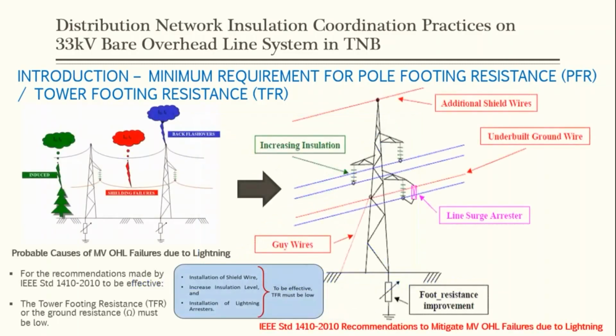All right. The probable causes for medium voltage overhead line failures due to lightning can be back flashovers, shielding failures, and induced overvoltage, right? And the IEEE 1410 recommendations to mitigate medium voltage overhead line failures due to lightning are using shield wires, increasing the insulation, installing line surge arresters, and improving the footing resistance. Okay. But for the recommendations made by IEEE standard 1410 to be effective, the tower footing resistance, or the ground resistance, must be low, because the installation of shield wire, increased insulation level, and installation of line arresters can be effective only with the TFR set to a very low measurement or value. Okay, so that will be a challenge for us.